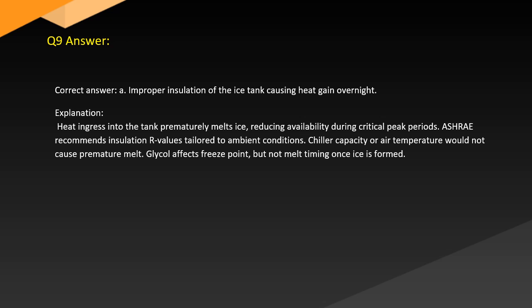Answer. Correct answer: A. Improper insulation of the ice tank causing heat gain overnight. Explanation. Heat ingress into the tank prematurely melts ice, reducing availability during critical peak periods. ASHRAE recommends insulation R-values tailored to ambient conditions. Chiller capacity or air temperature would not cause premature melt. Glycol affects freeze point, but not melt timing once ice is formed.